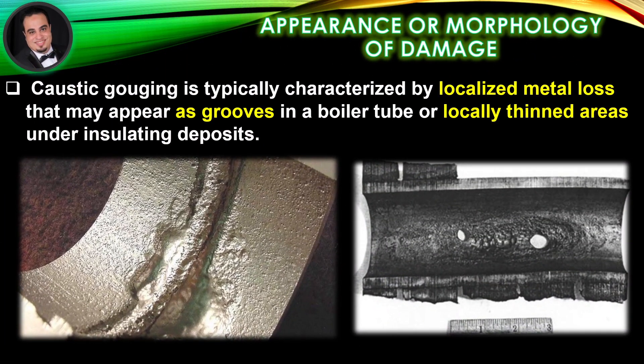Appearance or morphology of damage: As illustrated in figures, caustic gouging is typically characterized by localized metal loss that may appear as grooves in a boiler tube, or locally thinned areas under insulating deposits.